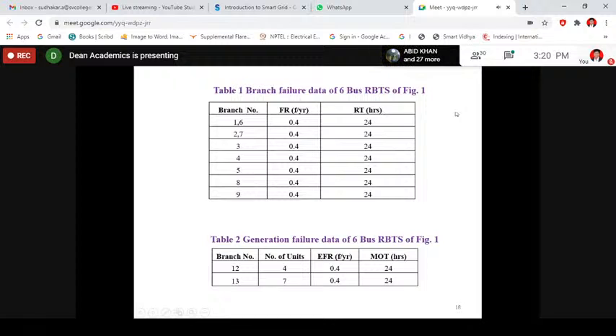Failure rate is failures per year, so 0.4 failures per year means the reciprocal of this is the mean time to failure, also called operable time. So 1 by 0.4 is 2.5. That means branch number 1 or 6 can fail at the rate of once in 2.5 years, i.e., the component is likely to get overloaded or start giving problems.